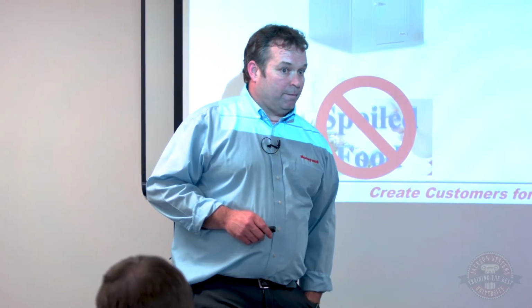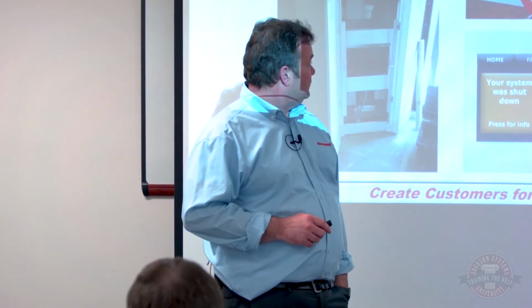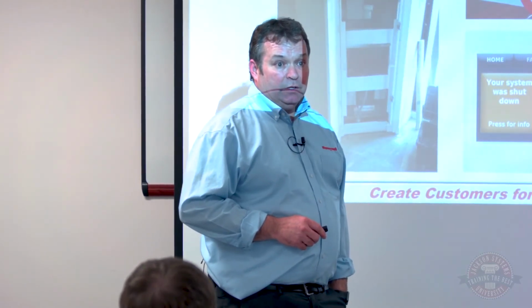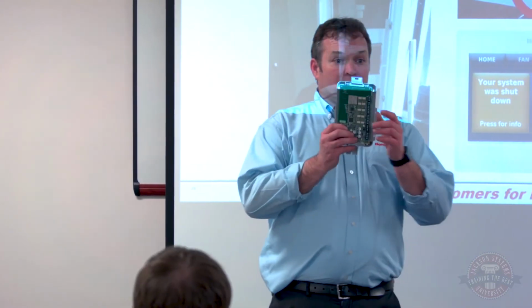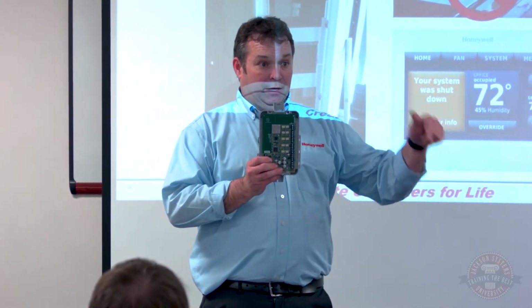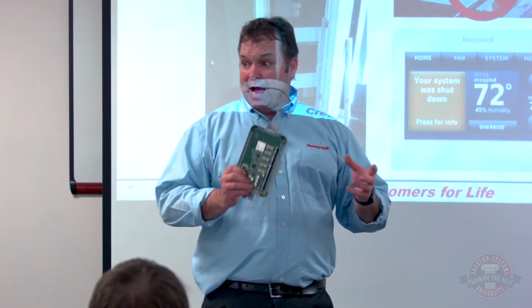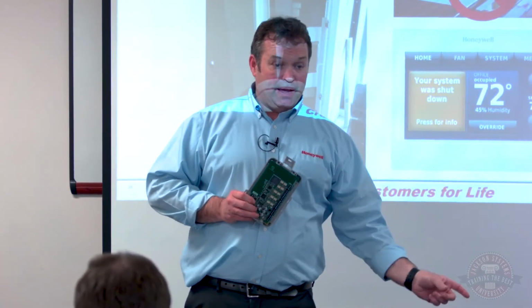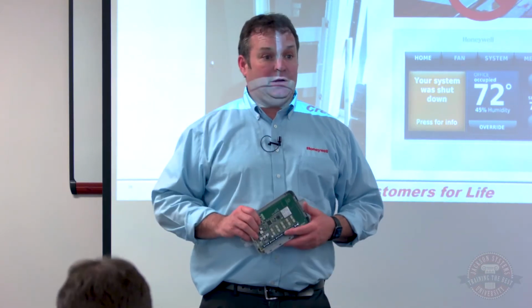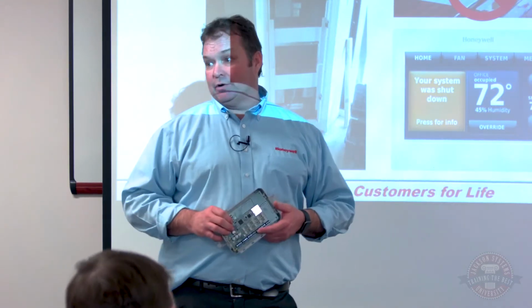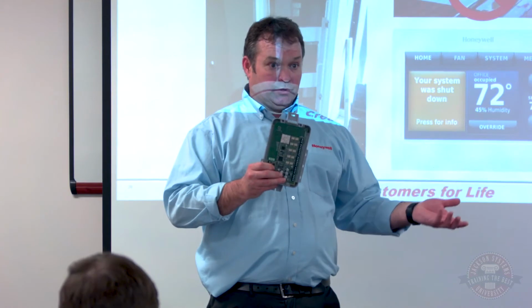On the drain pan alert, yes, it will shut off the unit if you want it to, but you have to choose system shutdown and put the float switch into this. That way it shuts off without killing the power. Because if I had a gateway and the float switch just killed power to the unit, I wouldn't get an email alert, it might shut off before the alert is generated. So use this with system shutdown to shut your equipment down without killing the power.